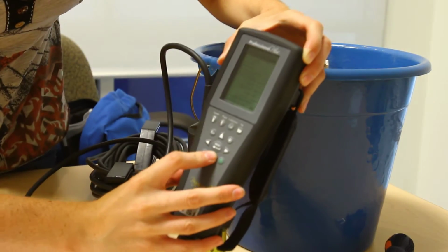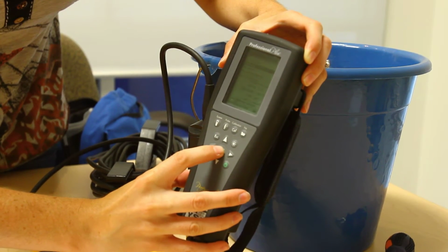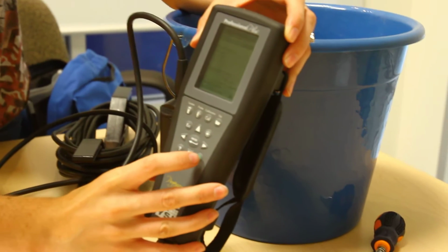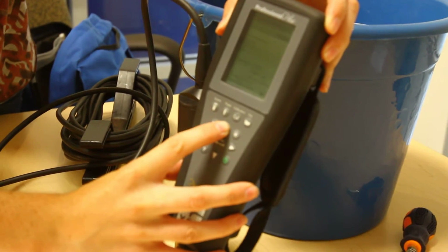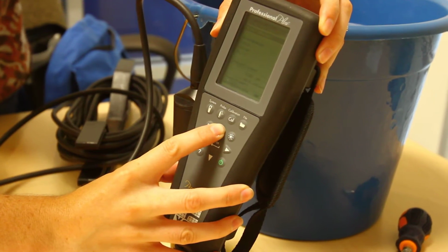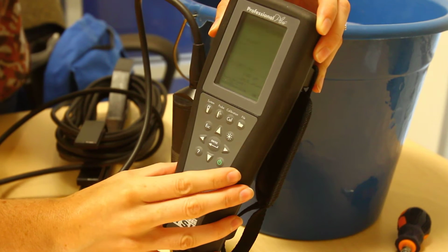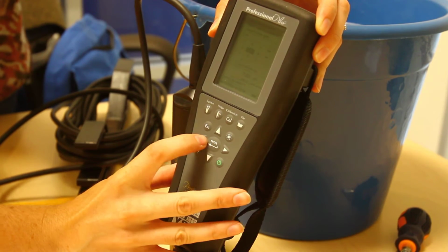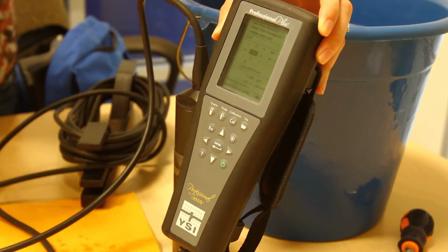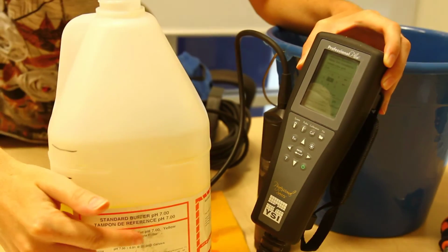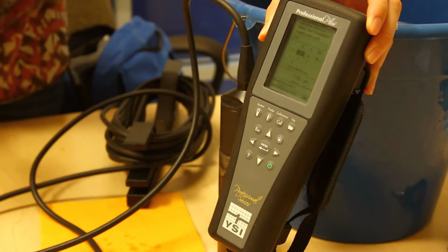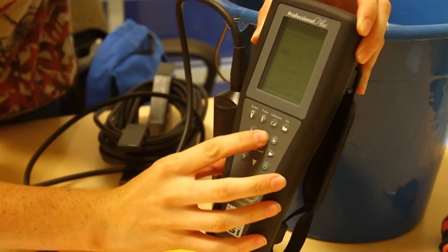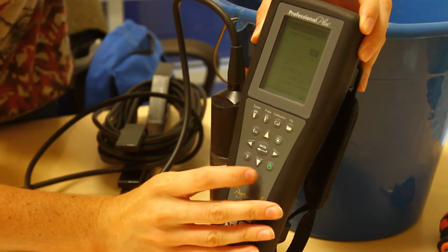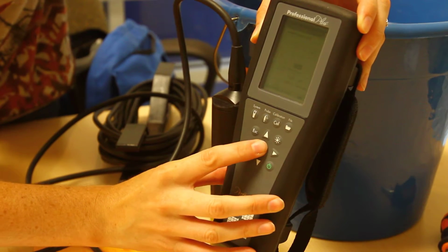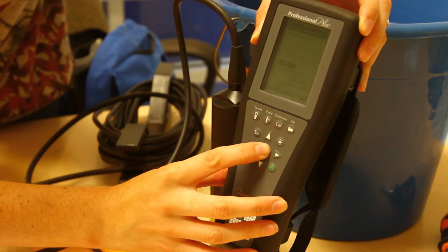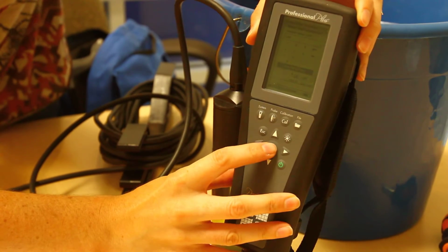Scroll to pH and press Enter. If you do need to adjust the calibration value, scroll to Calibration Value and press Enter. This number should reflect the value that's found on the bottle. In this case, for a buffer standard for pH 7, you're looking for 7.00. Once finished, highlight Enter and press Enter.